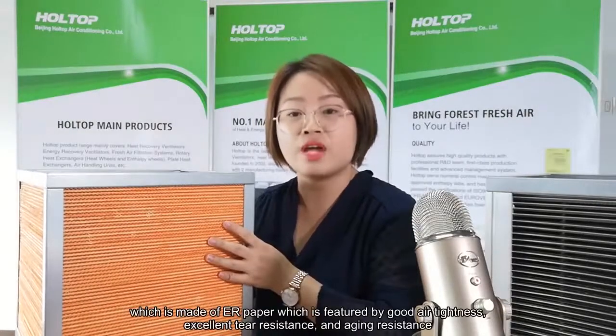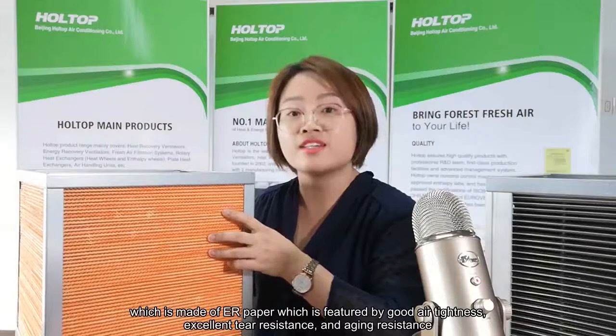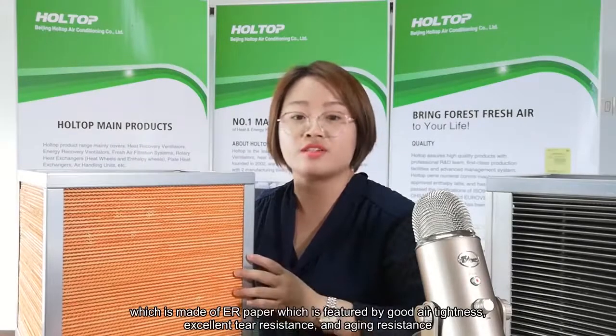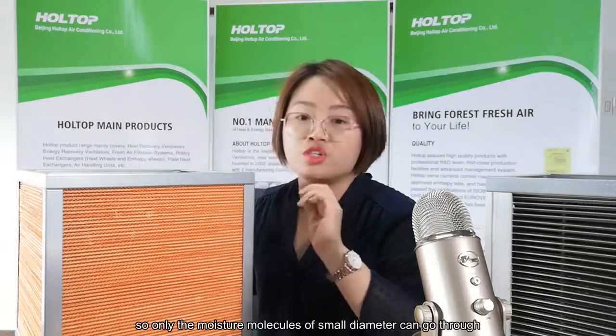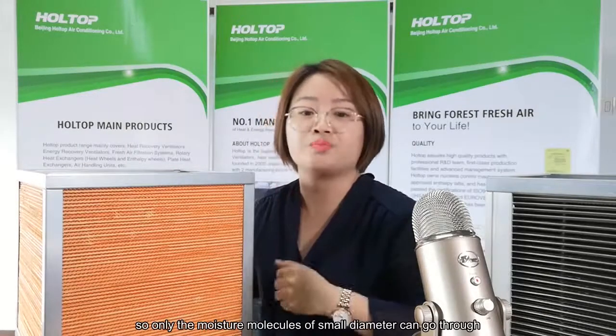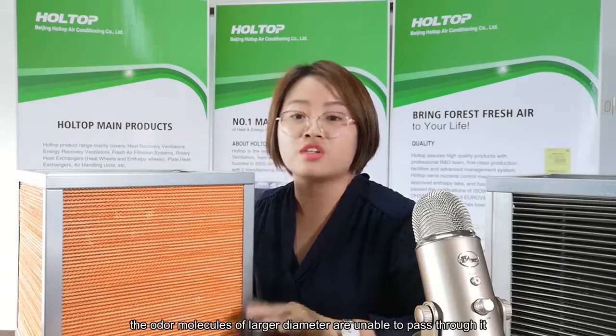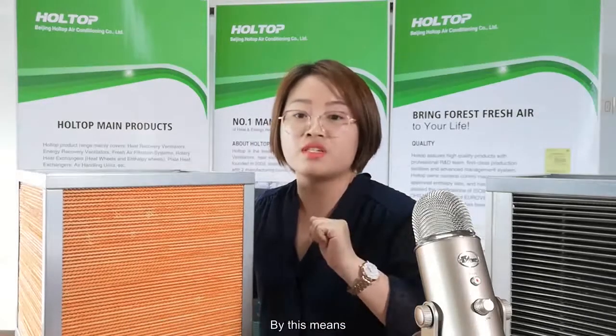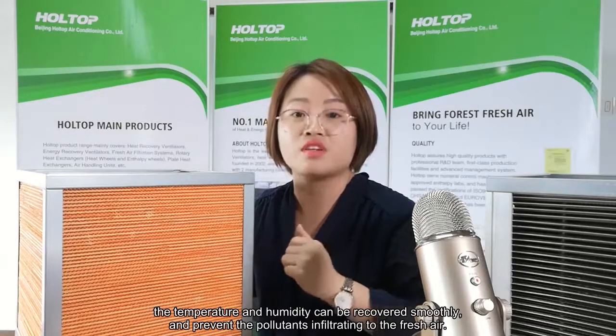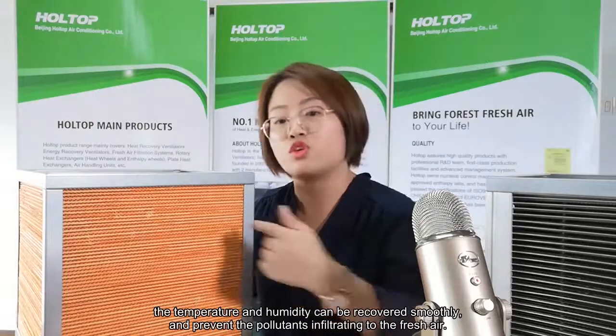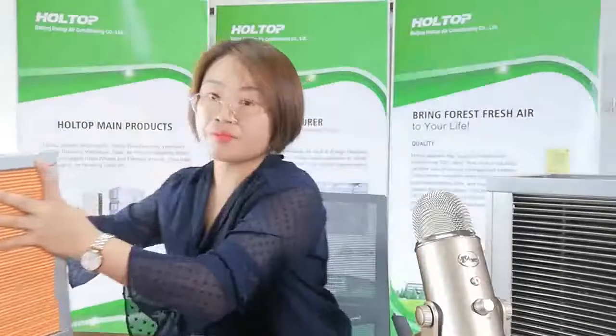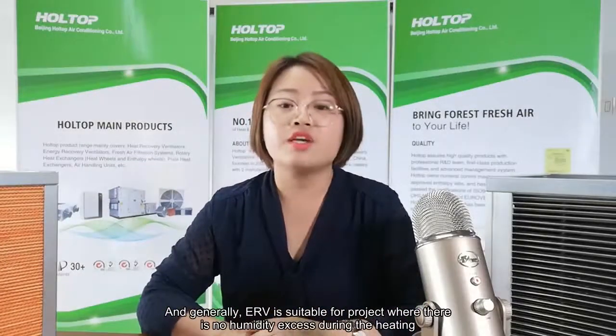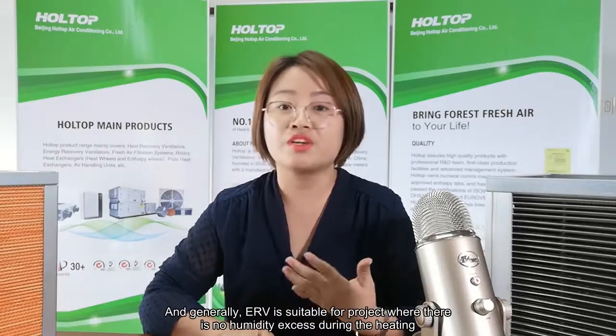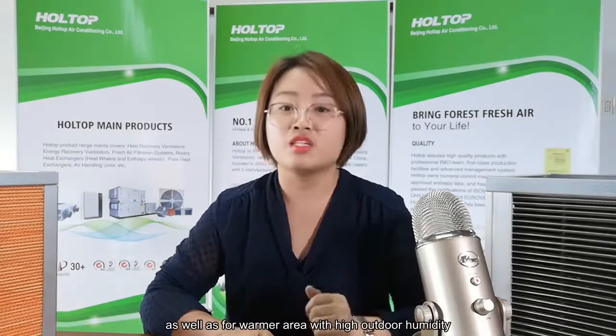It is made of ER paper and is featured by good air tightness, excellent tear resistance, and aging resistance. The clearance between the two fibers is very small, so only the moisture molecules of small diameter can go through it. The other molecules of larger diameter are unable to pass through. By this means, the temperature and the humidity can be recovered smoothly, and pollutants are prevented from infiltrating the fresh air. And generally, the ERV is suitable for projects where there is no humidity excess during the heating, as well as for warmer areas with high outdoor humidity.